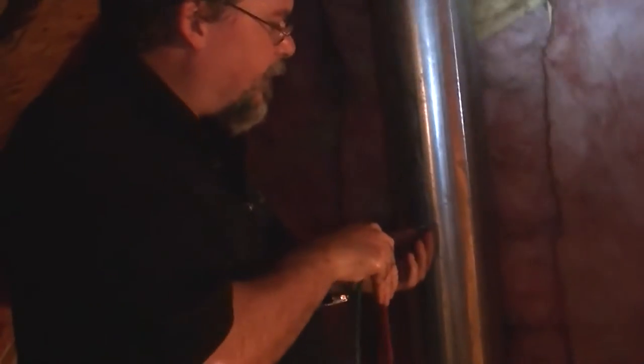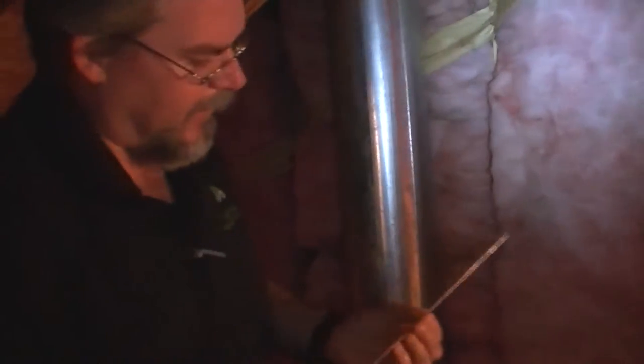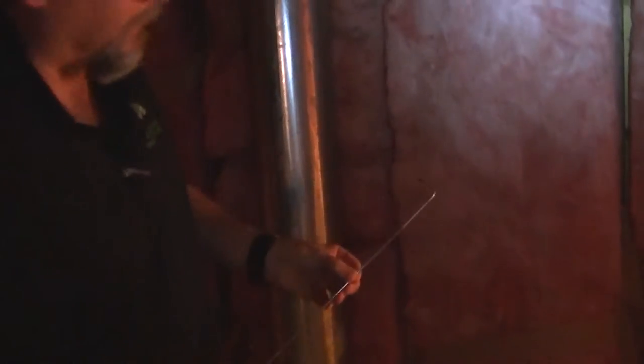The other thing I need to figure out is the diameter of this duct. We need the inside diameter. One simple way is to insert the pitot tube until it presses against the other side of the duct, pull it out, and measure the difference.